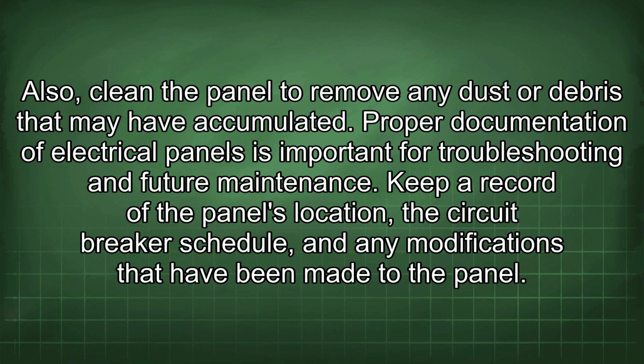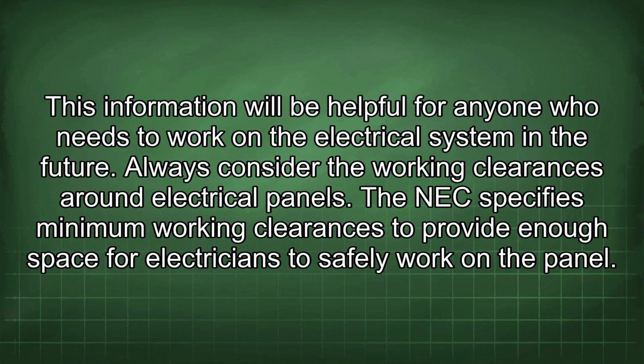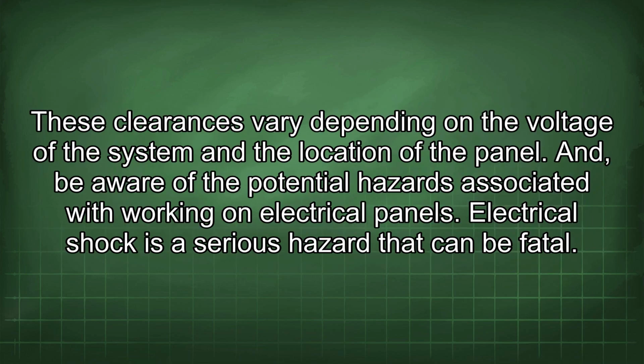Proper documentation of electrical panels is important for troubleshooting and future maintenance. Keep a record of the panel's location, the circuit breaker schedule, and any modifications that have been made to the panel. This information will be helpful for anyone who needs to work on the electrical system in the future. Always consider the working clearances around electrical panels. The NEC specifies minimum working clearances to provide enough space for electricians to safely work on the panel. These clearances vary depending on the voltage of the system and the location of the panel.